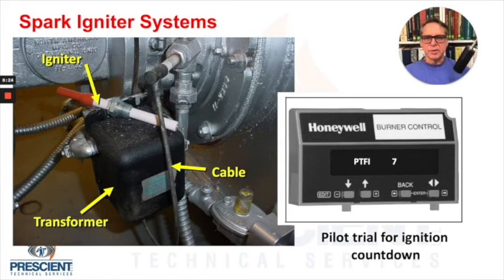If you ever remove one of these, by loosening the crush sleeve, make sure you mark it with a marker so you know the proper insertion depth. Reasons that you might not be lighting off could include the fact that that tip is worn and needs to be cleaned or needs to be replaced or needs to be readjusted. You also want to check cables, make sure that they're securely installed and that the ignition transformer is still functioning.